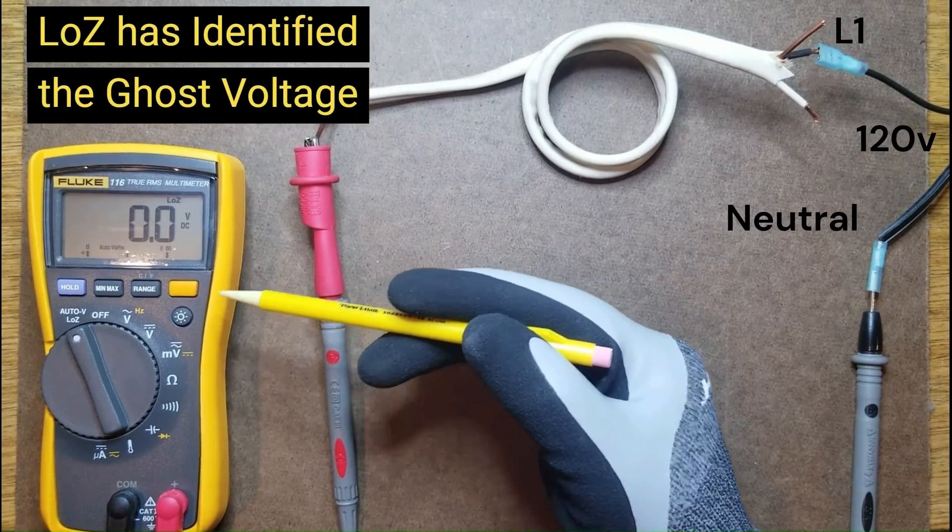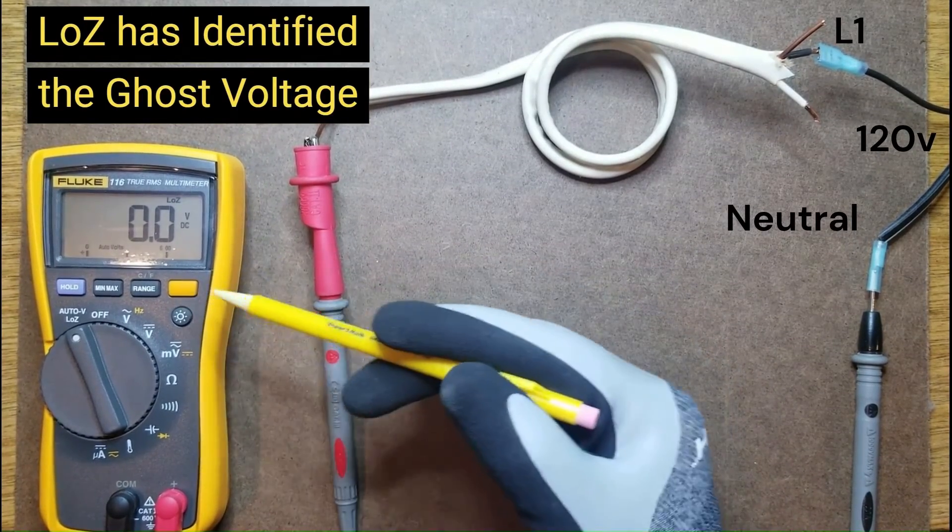Therefore, by using low Z, we have easily determined that what we were reading was a ghost voltage.